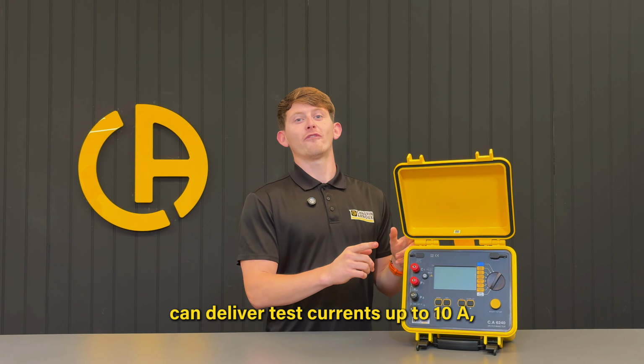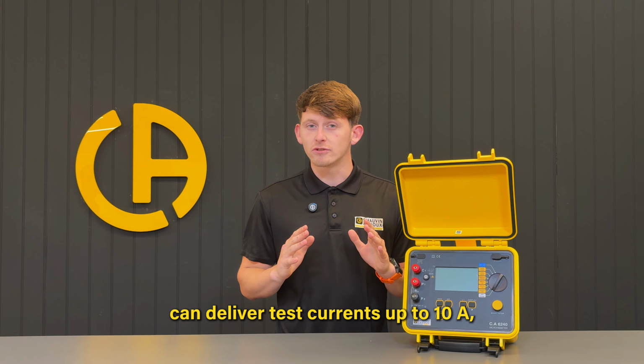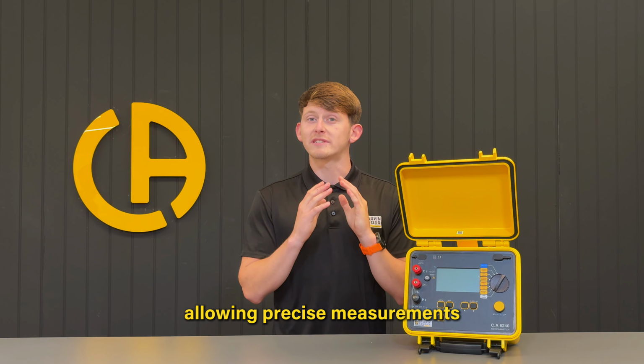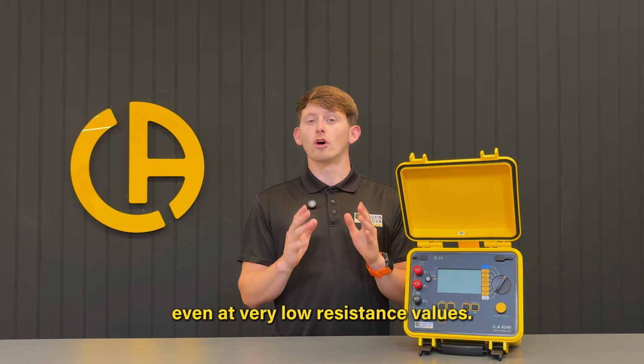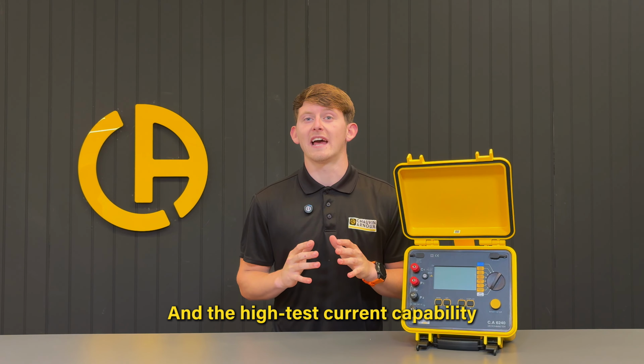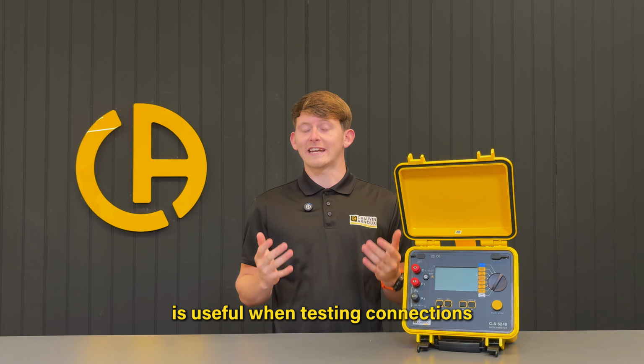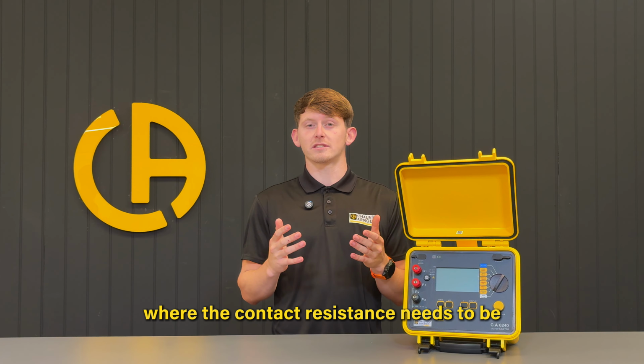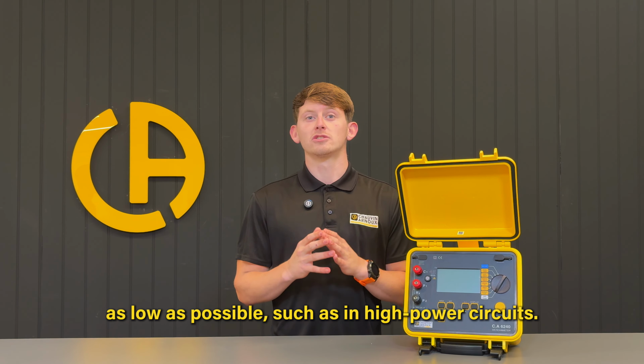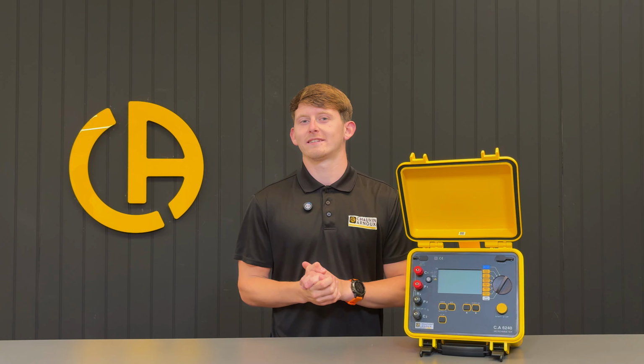The CA 6240 can deliver test currents up to 10 amps, allowing precise measurements even at very low resistance values. The high test current capability is useful when testing connections where the contact resistance needs to be as low as possible, such as in high power circuits.